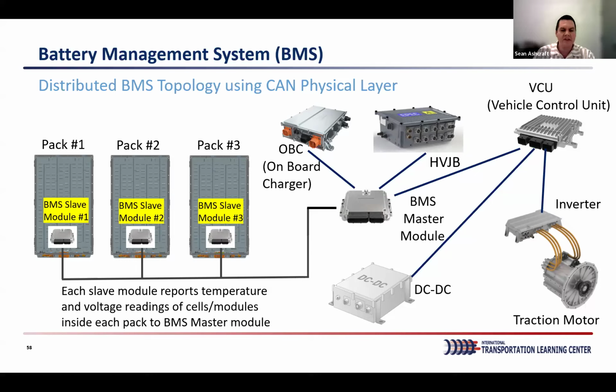Inside each of the three battery packs in this example live the BMS slave modules. The module's role is to record physical data measurements of cell voltages and temperatures, and also perform cell balancing. Each slave module's CAN communication wires are daisy chained from pack to pack, and ultimately back to the BMS master module, located in the middle of the slide. The master module processes all the data from the slave modules and is programmed with logic to make decisions such as setting charging and discharging limits.